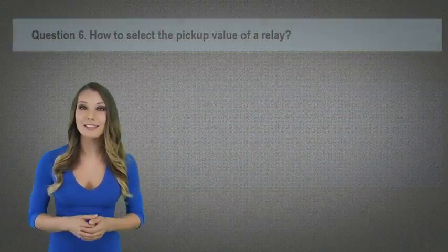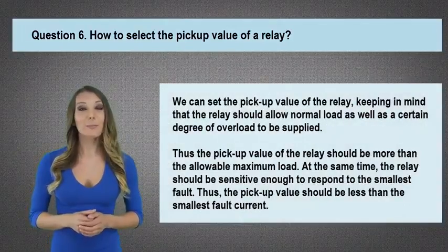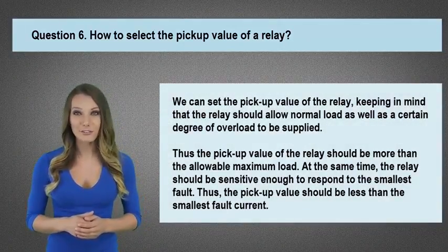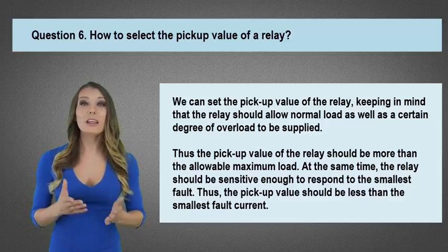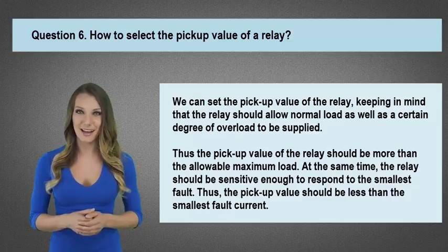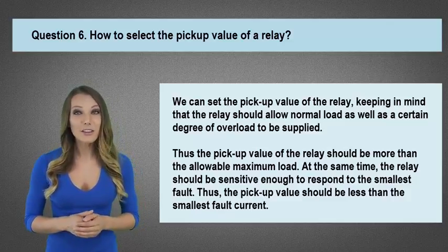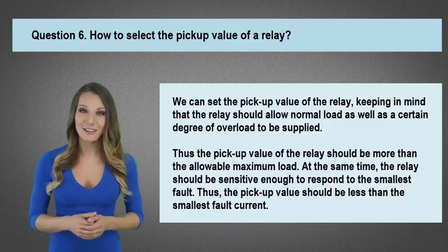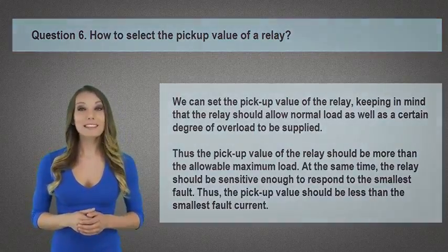Question 6. How to select the pickup value of a relay? We can set the pickup value of the relay, keeping in mind that the relay should allow normal load as well as a certain degree of overload to be supplied. Thus the pickup value of the relay should be more than the allowable maximum load. At the same time, the relay should be sensitive enough to respond to the smallest fault. Thus, the pickup value should be less than the smallest fault current.